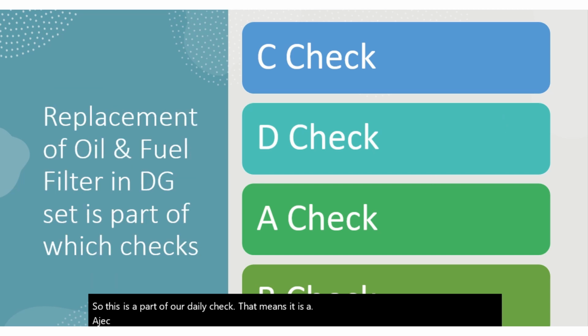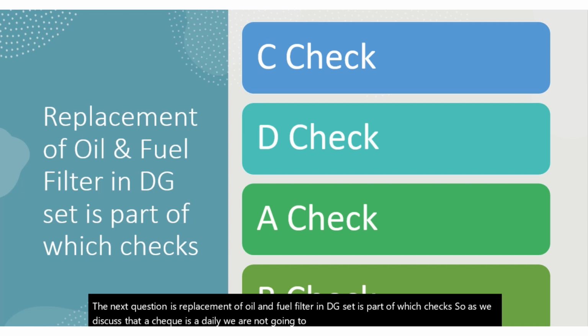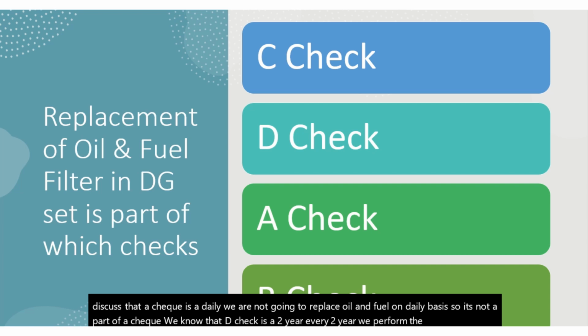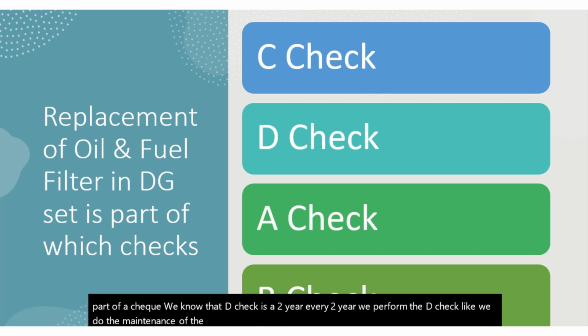The next question is: replacement of oil and fuel filter in DG set is part of which checks? As we discussed, A check is daily, and we are not going to replace oil and fuel filters on a daily basis, so it's not part of A check. We know that D check is performed every 2 years, like the maintenance of the turbocharger and air compressors. Even fuel tank cleaning is not part of this, so it is not a D check.